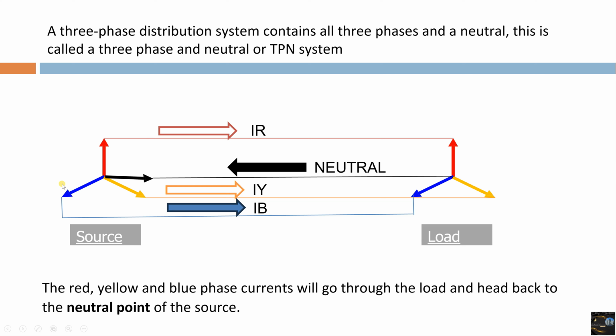Here, if you see, we have a source, a three-phase source. We have a three-phase load. You can see the red phase, yellow phase, and blue phase currents go towards the load side. And we also have a neutral system that heads back to the neutral point of the source. So this is our typical three-phase system and we call it a TPN system. N stands for neutral and P is for phase.